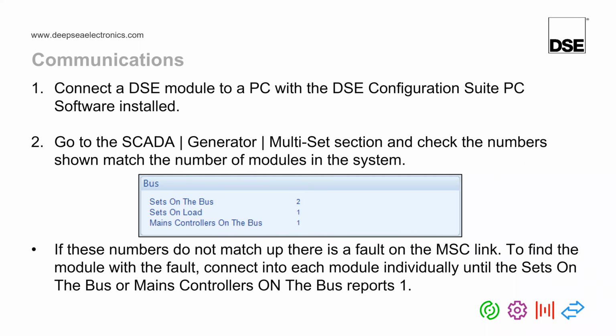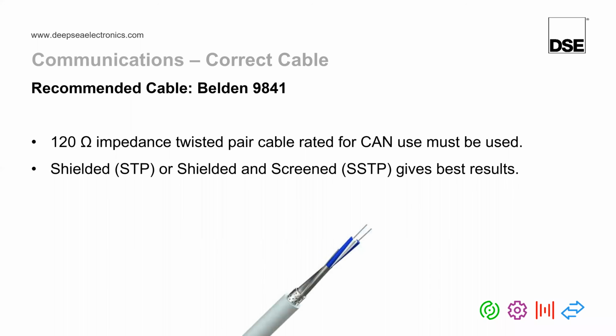So let's just do a bit of housekeeping and talk about what could cause MSC failures. The most common MSC failure we find is people using the incorrect type of cable. The cable you should be using for MSC communication is CAN bus rated cable. The cable we recommend is from a manufacturer known as Belden, and its part number is 9841. This cable has a very special characteristic, which is a 120 ohm impedance, and again is suitable for CAN bus communication. The cable we also advise should be shielded or screened and shielded.